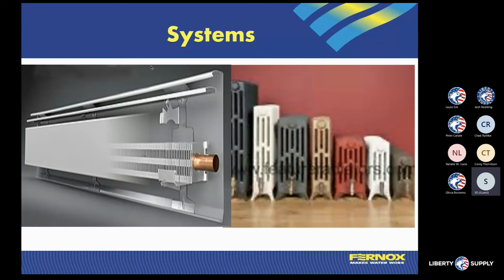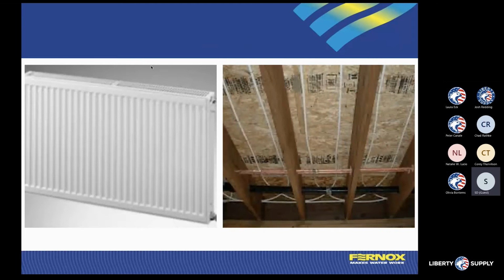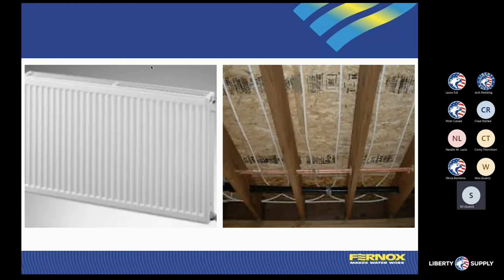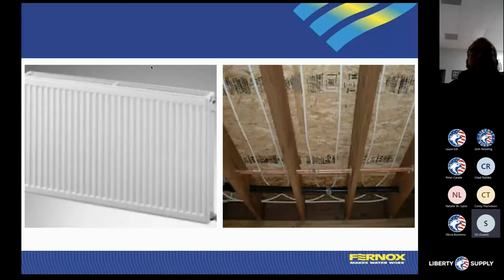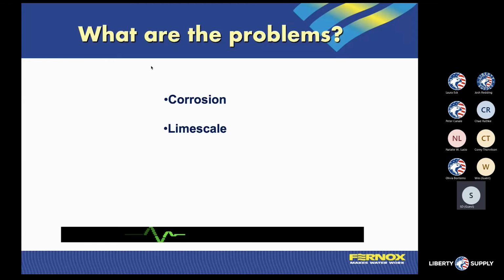So we're going to work with all the different types of metals out there, whether it's a cast iron radiation fin tube, whether it's a PEX or a steel radiator, such as a panel radiator. All of these types of systems are going to be components that we're going to need to deal with water quality. No matter what the system is, if we have mineral or any kind of broken down sediment, we're essentially going to be etching at the inside of the piping system. So even if nothing else is off, we're still going to be eroding that internal system based upon the mineral and obviously the coarseness of that product that's going to be inside of your heating system.